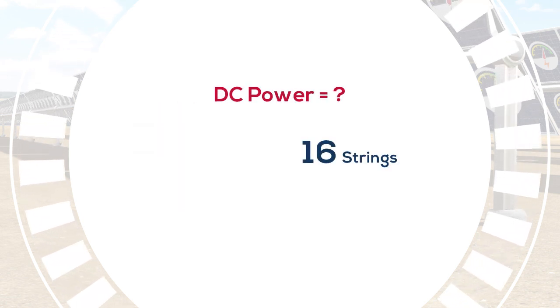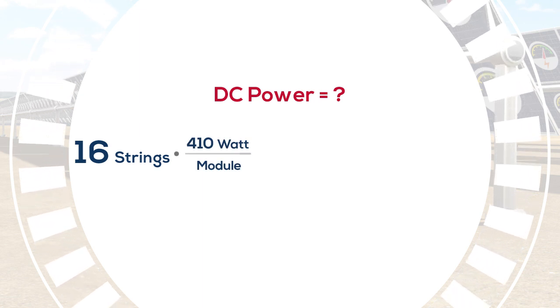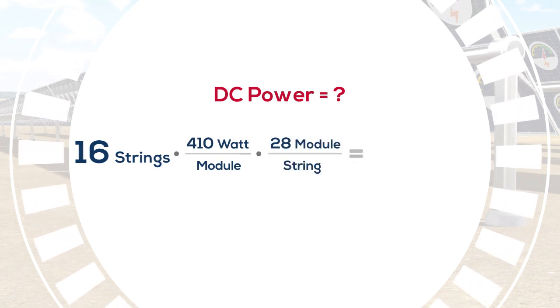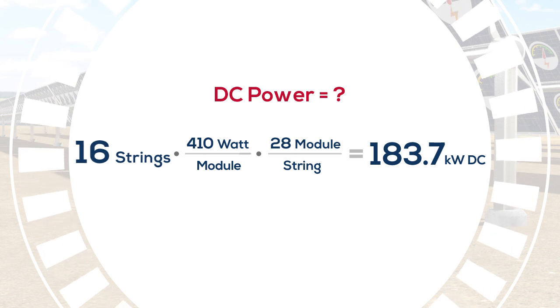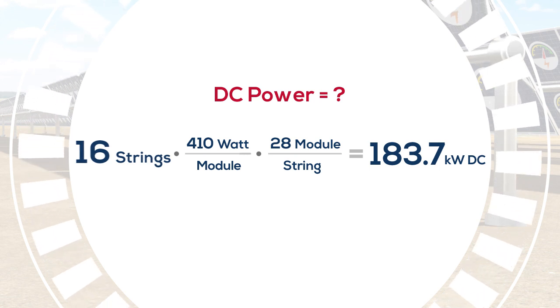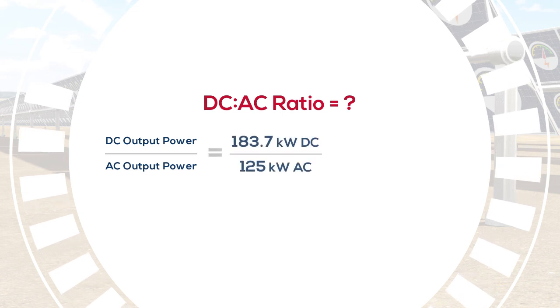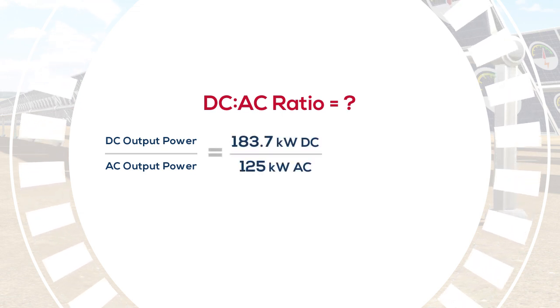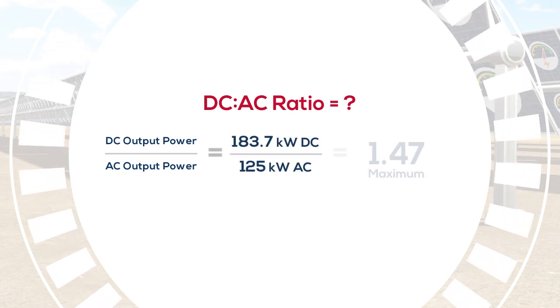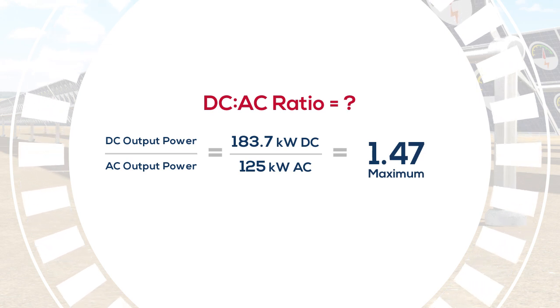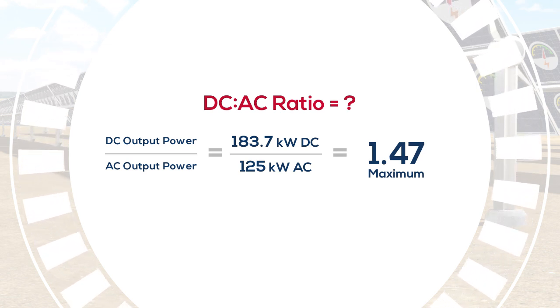The DC power is 16 strings times 410 watts per module times 28 modules per string, which yields 183.7 kilowatts DC. The maximum DC to AC ratio is then 183.7 kilowatts divided by 125 kilowatts, which yields 1.47. This gives you lots of room to optimize your project.